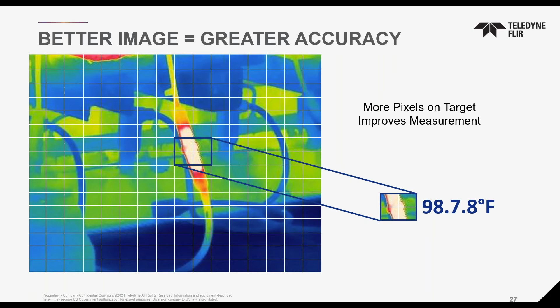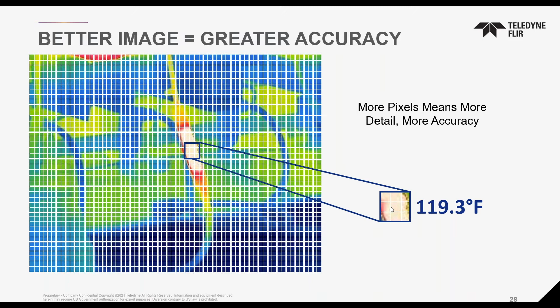Now if we get even more pixels on that target, now we got 9 pixels inside of that same space that we've been looking at. Now we're getting a reading of 119 degrees, because each one of these pixels is small enough that it's just hitting the hot spot of that wire and not bringing in as much of the green and the blue into the scene. The pixel is small enough that it's picking up exactly what is on that wire, which is our region of interest. So we went from 79 degrees all the way up to 119 degrees, so 40 degrees higher or more accurate, just by getting more pixels on target. So when you're shopping for your thermal camera, it's important that for your application, you have a camera that will give you an accurate enough reading, with enough pixels to fully do your work.